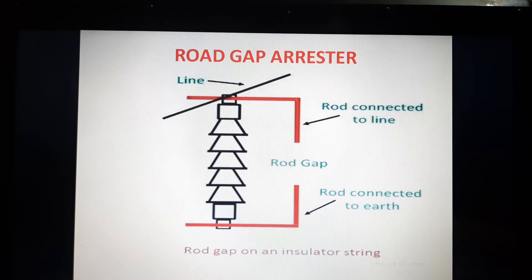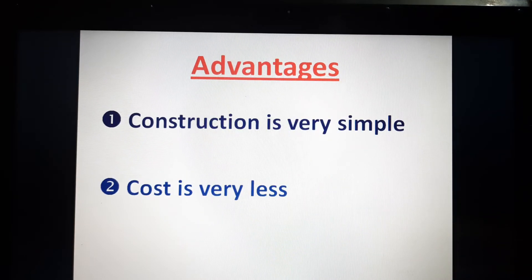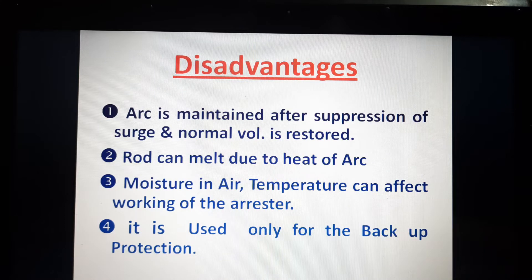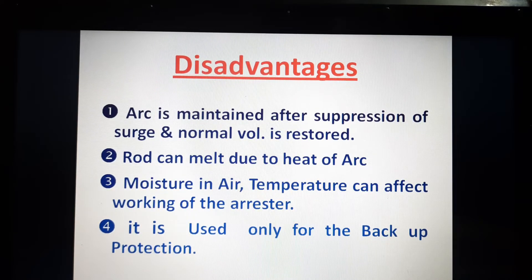The construction of the rod gap arrestor is very simple and its cost is very low compared to other lightning arrestors. However, there are a few disadvantages. First, the arc is maintained after suppression of the surge even when normal voltage is restored. Second, the rod can melt due to the heat of the arc, as the high temperature caused by the arc can melt the rod.